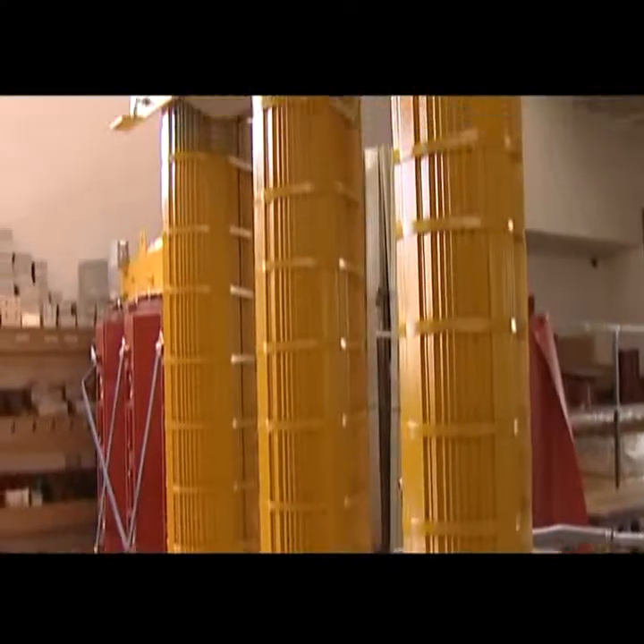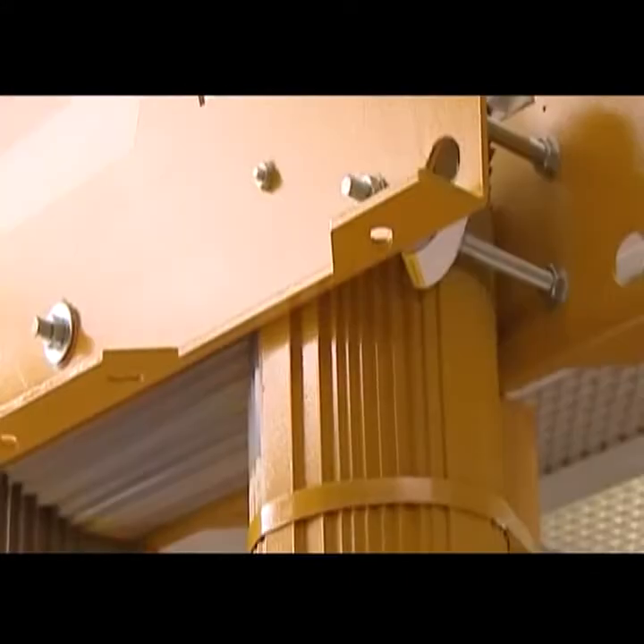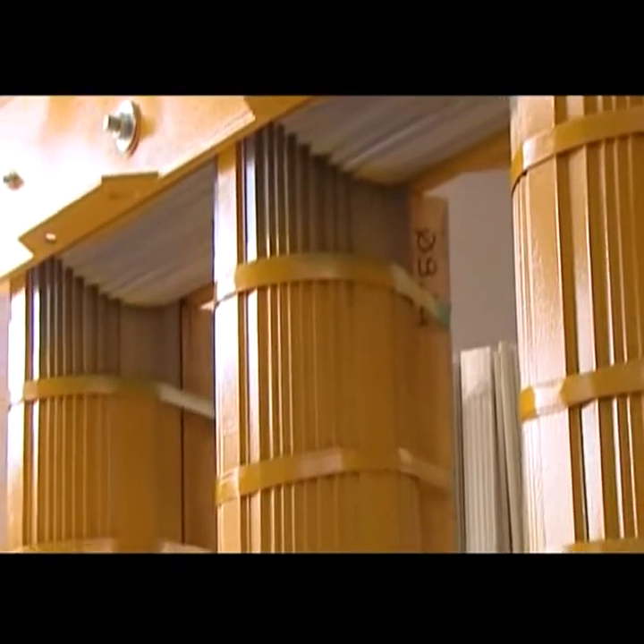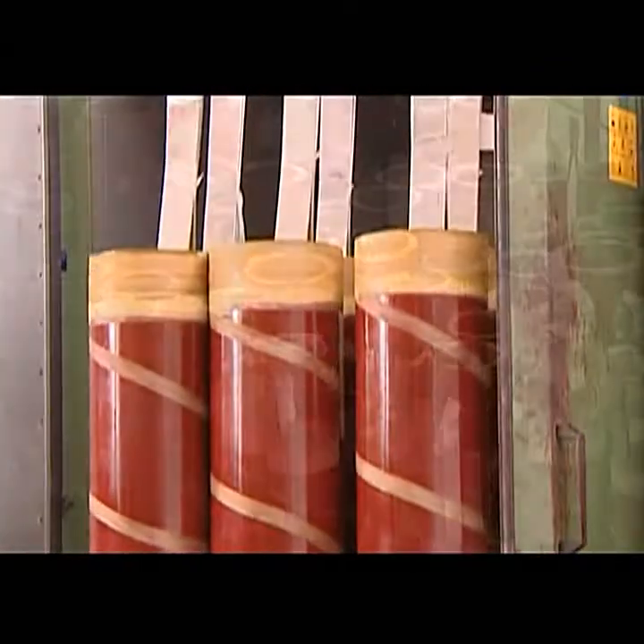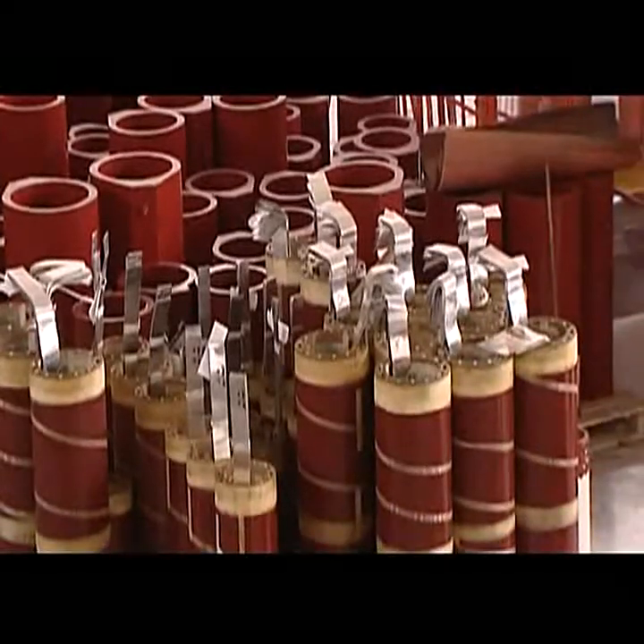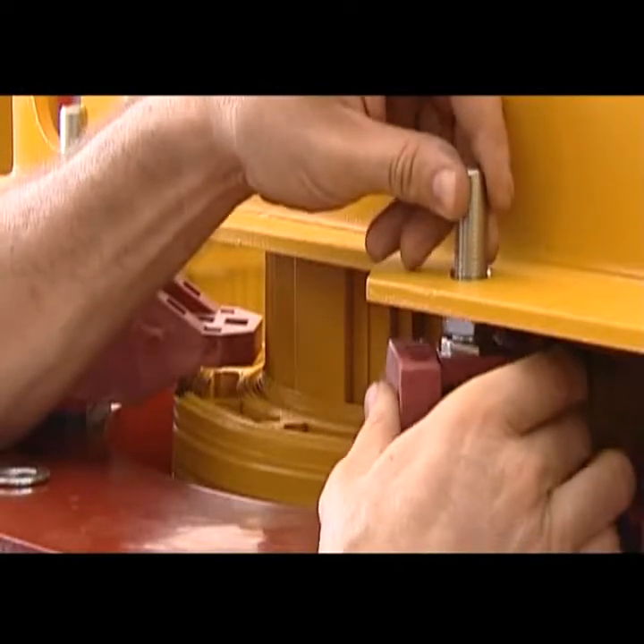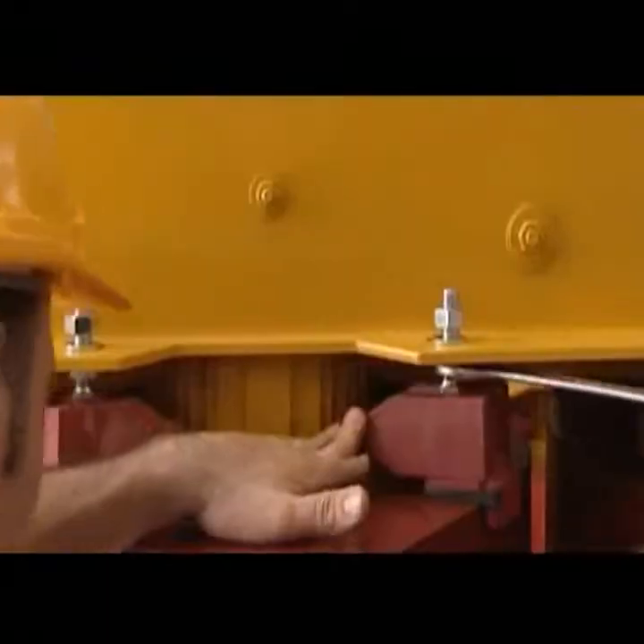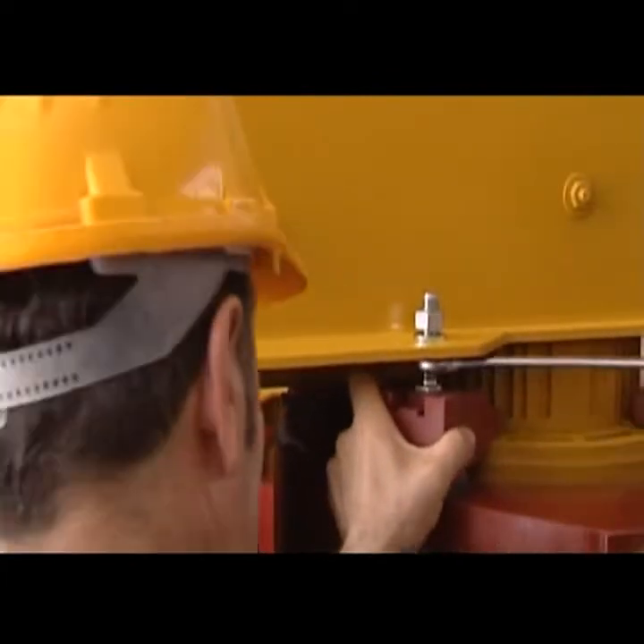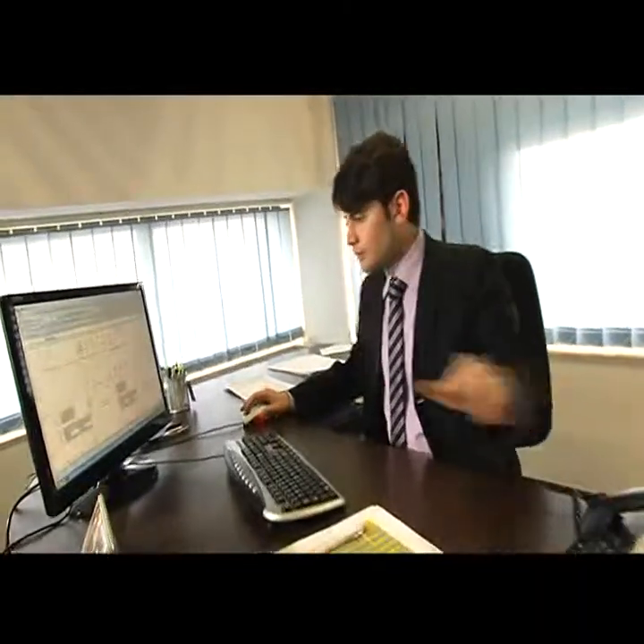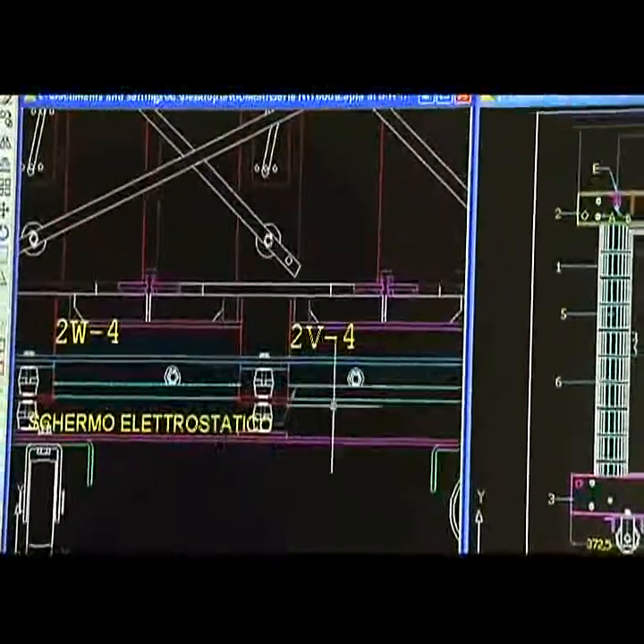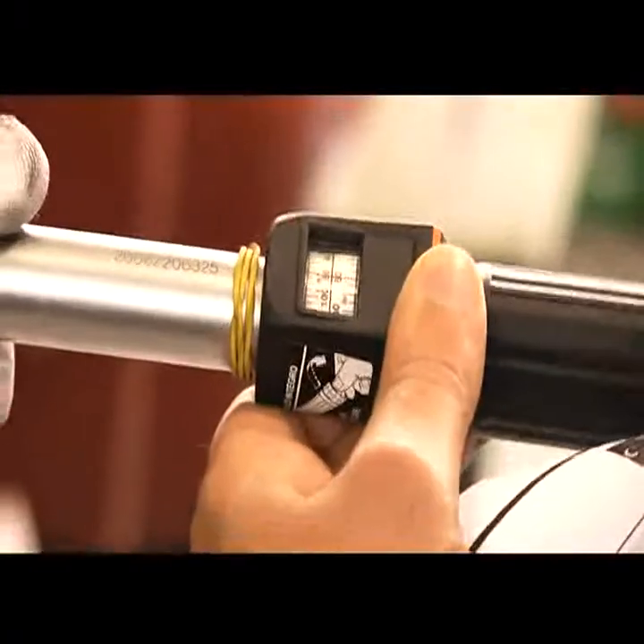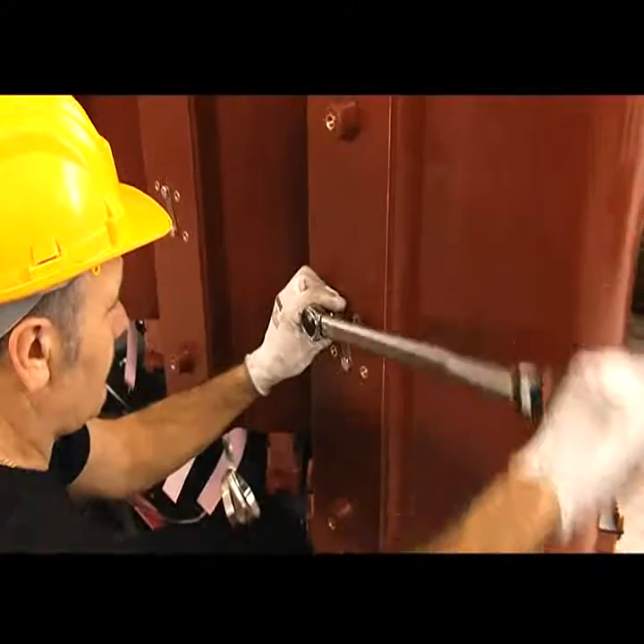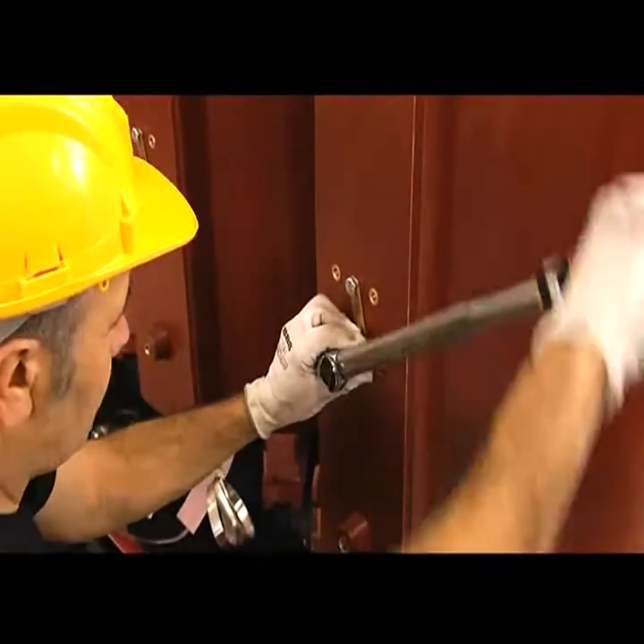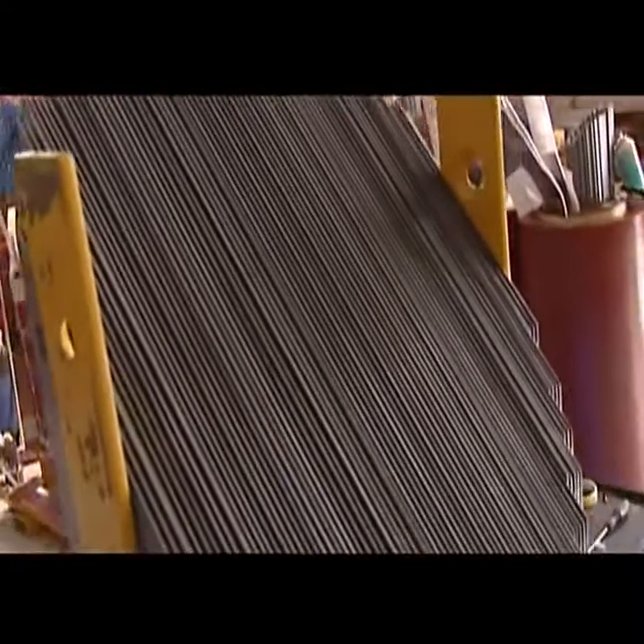The main assembly parts of a cast resin transformer, having primary in medium voltage, are the magnetic core, the low and medium voltage windings, the accessories and the metal carpentry support, the insulating system of active parts. ALTRAFO deals with the design of transformer components and produces windings, encapsulation in resin, electric connection system exterior to the machine, assigns skilled suppliers the task to look after laminations cut and their assembling to core metal structure.